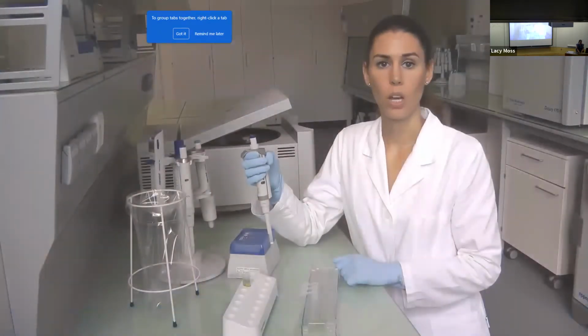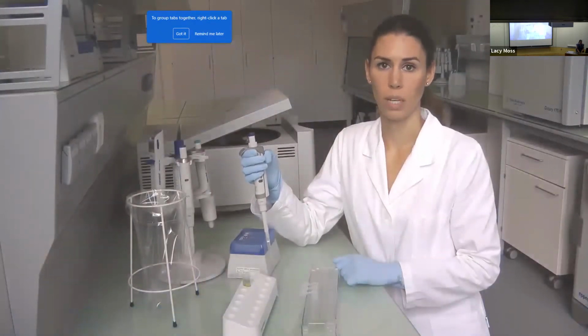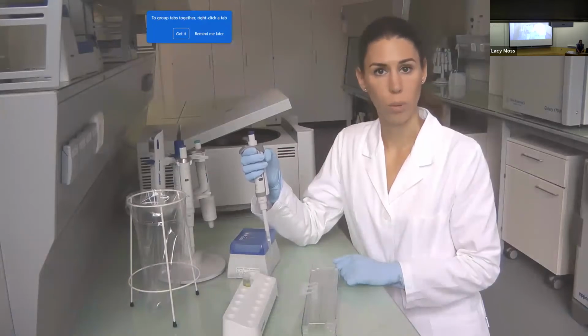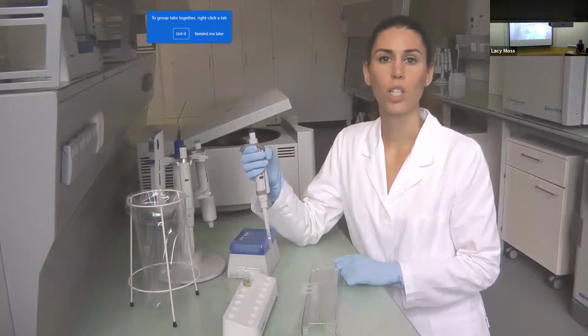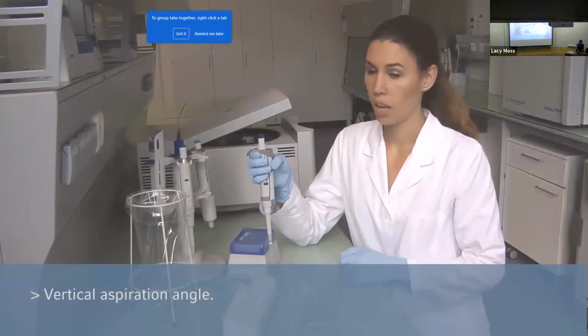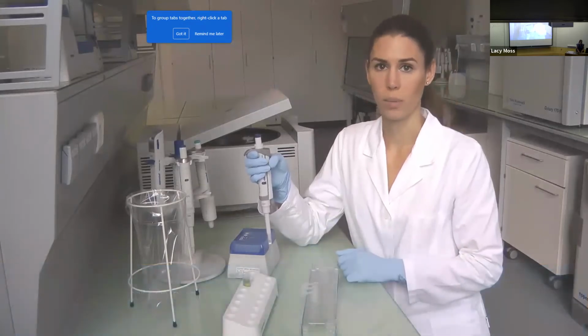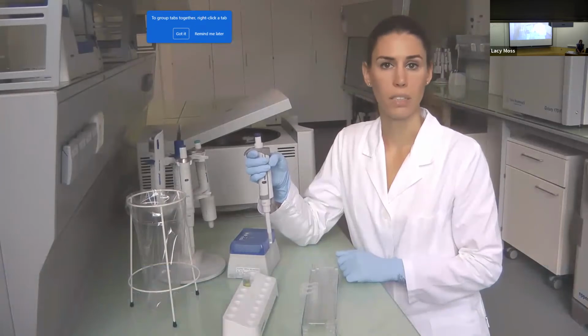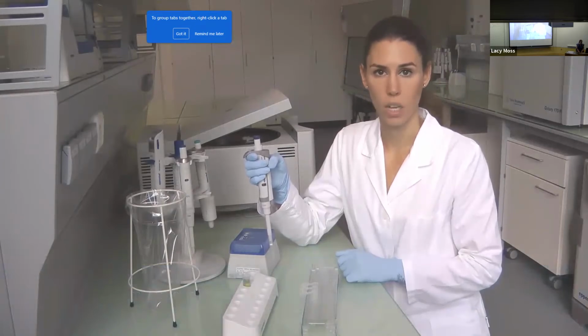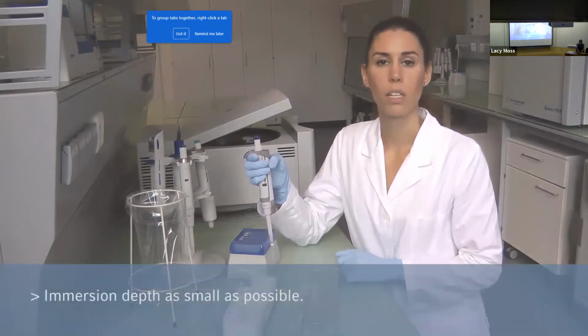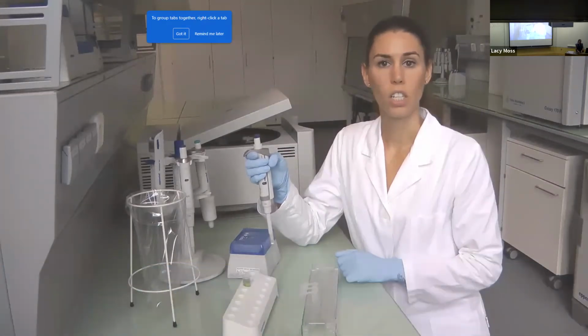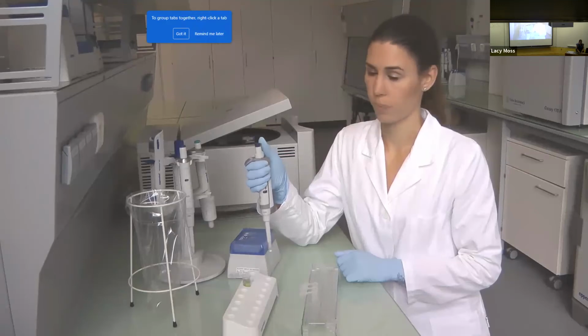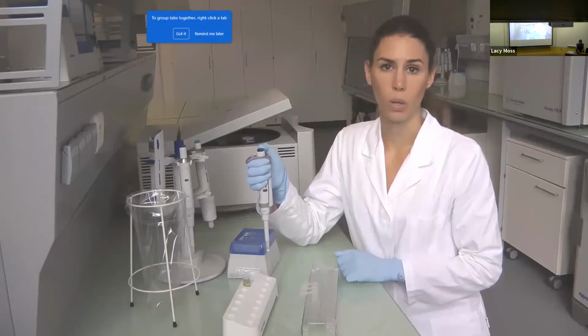When aspirating liquid, 2 factors influence accurate liquid uptake: the aspiration angle and the immersion depth. The aspiration angle should be vertical. Otherwise, too much liquid is aspirated. The immersion depth, meaning the depth of the pipette tip inside the liquid, should be as large as necessary, but as small as possible. If the tip is immersed too deeply, additional liquid can be easily aspirated due to the capillary effect.